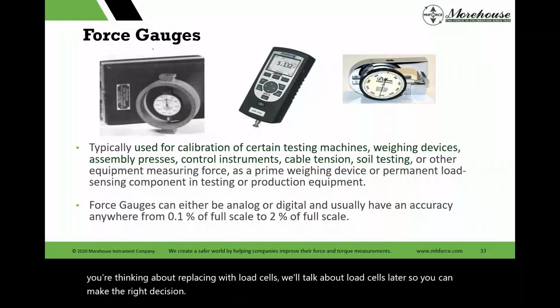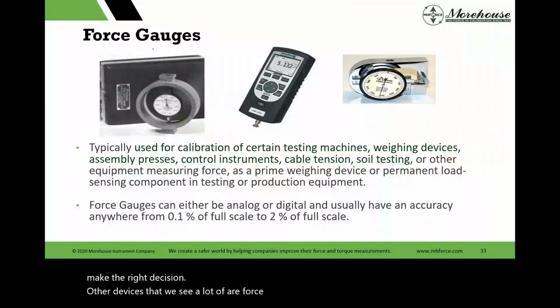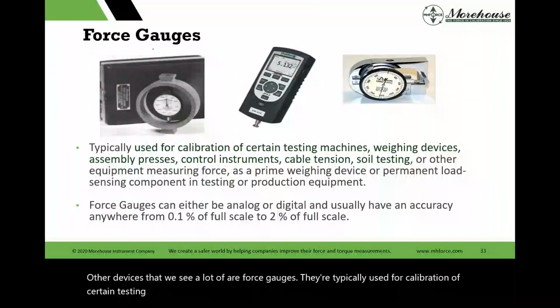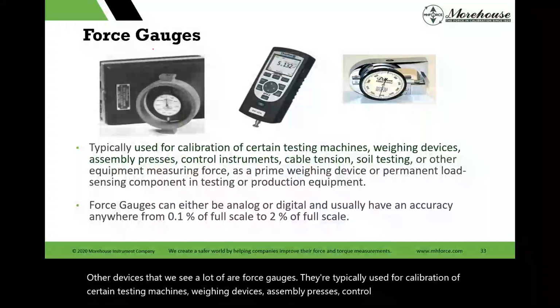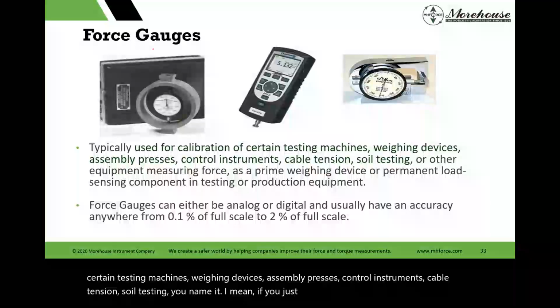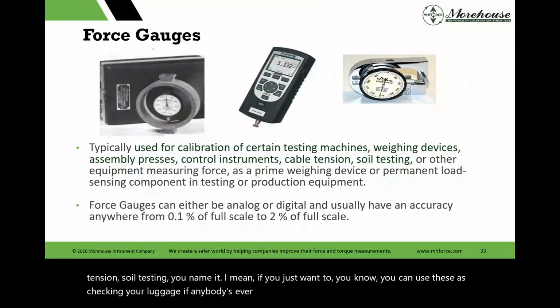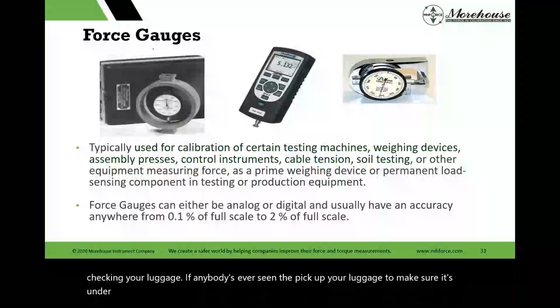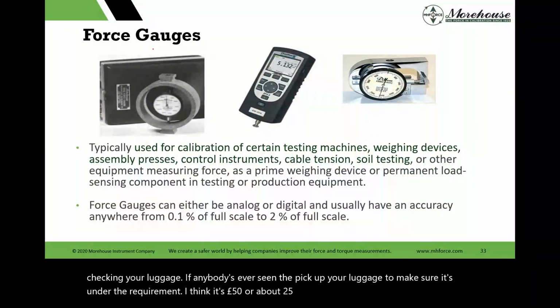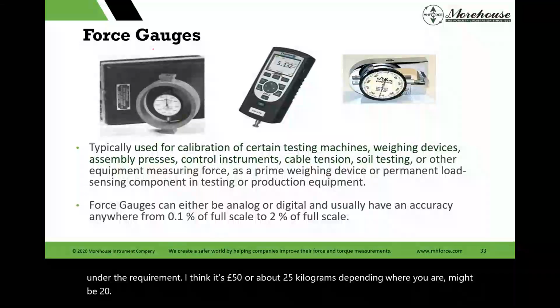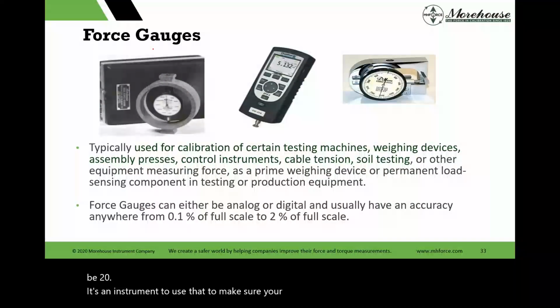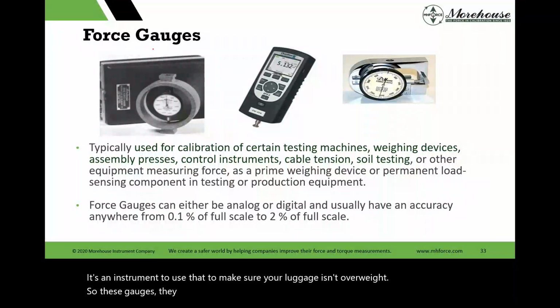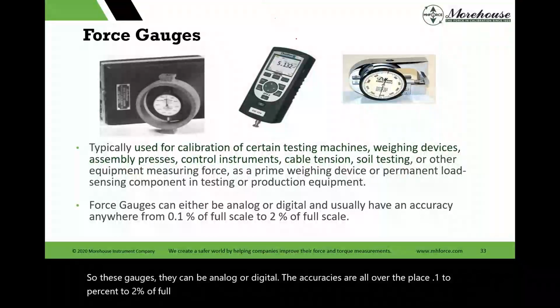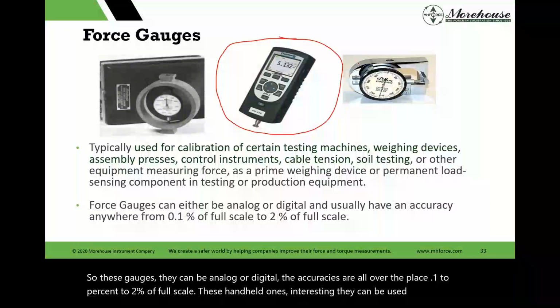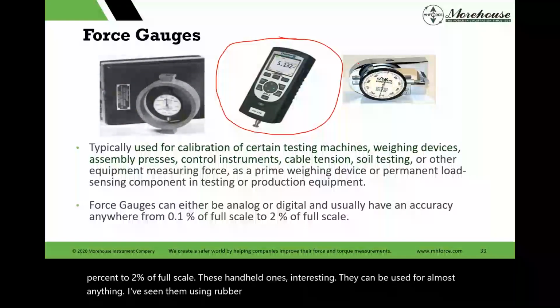Other devices that we see a lot of are force gauges. They're typically used for calibration of certain testing machines, weighing devices, assembly presses, control instruments, cable tension, soil testing, you name it. If you want to, you can use these for checking your luggage, if anybody's ever seen the pick-up-your-luggage check to make sure it's under the requirement. I think it's 50 pounds or about 25 kilograms, depending where you are, it might be 20. It's an instrument to make sure your luggage isn't overweight. So these gauges can be analog or digital. Accuracies are all over the place, 0.1% to 2% of full scale. These handheld ones, interesting, can be used for almost anything. I've seen them used in rubber applications, just seen them used everywhere.